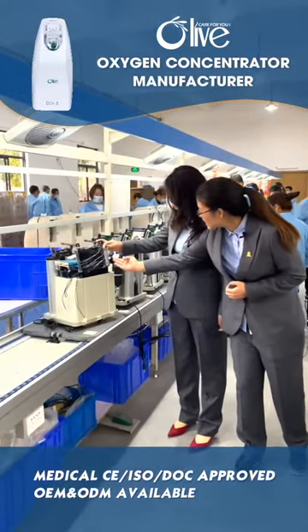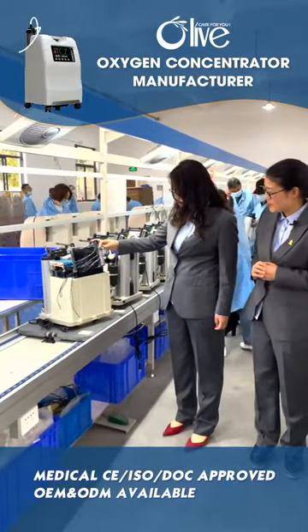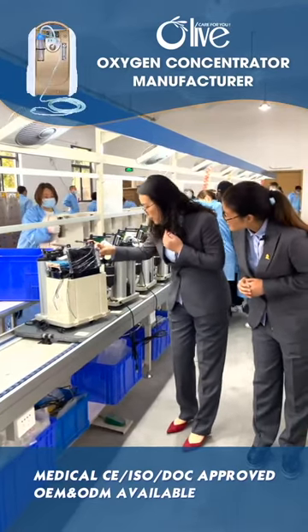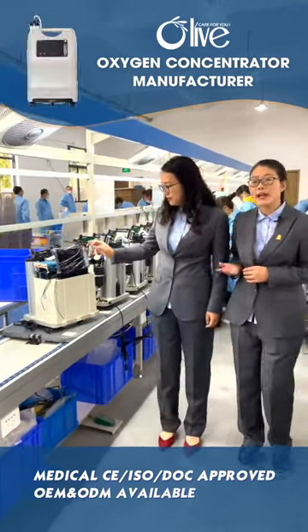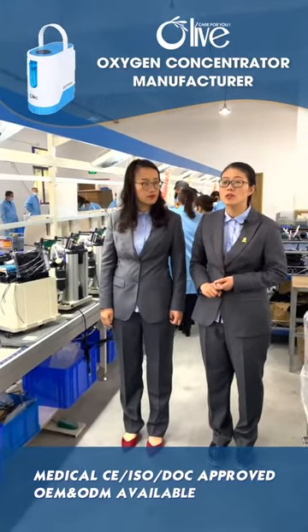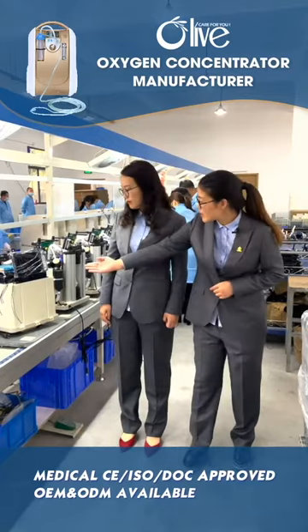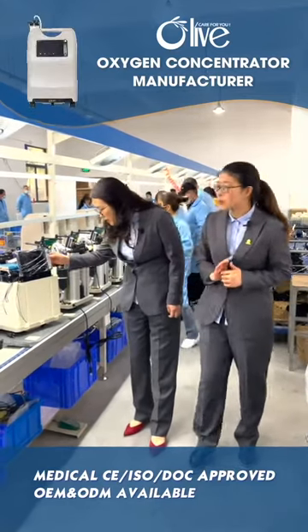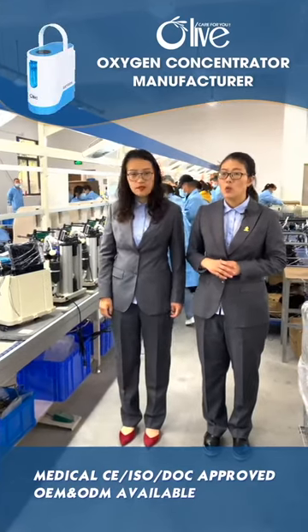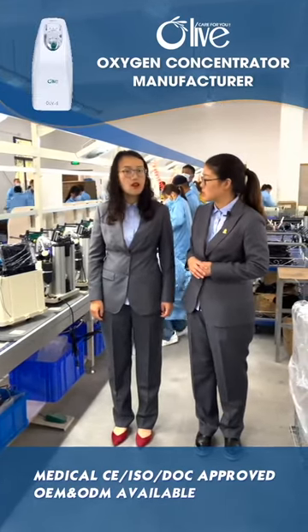On the side part, it's the flow meter. I saw there are numbers on the flow meter. Yes, because like I told you, we have 5 liter and 10 liter oxygen concentrators. For this one, you can check. The number is from 0 to 10, right? Yes, to 10. So we call it a 10 liter oxygen concentrator.